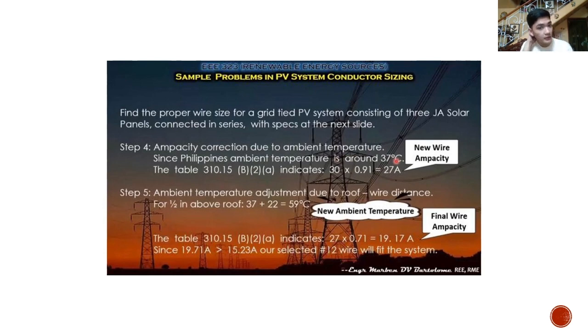Step 4, ampacity correction due to ambient temperature. Since Philippines ambient temperature is around 37 degrees Celsius, the table indicates 30 times 0.9 equals 27 ampere. Step 5, ambient temperature adjustment due to roof wire distance. For one half and above roof, 37 plus 22 equals 59 degrees Celsius.